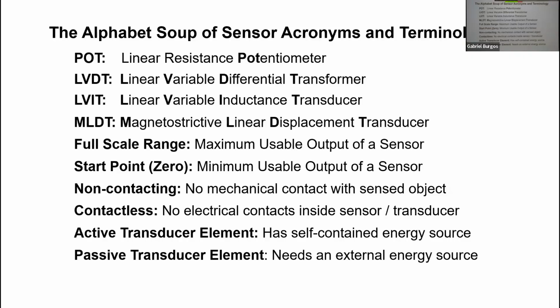MLDT, now that's been messed around with for a number of years. Basically, it's a fancy word for magnetostrictive linear displacement transducers. There are half a dozen manufacturers in this country and in Germany that make these things, a couple of them in Japan. Basically, they're high precision, long measuring range type devices that use a toroidal magnet to be able to assess the position of the magnet along an extended probe. So we'll talk about that later.